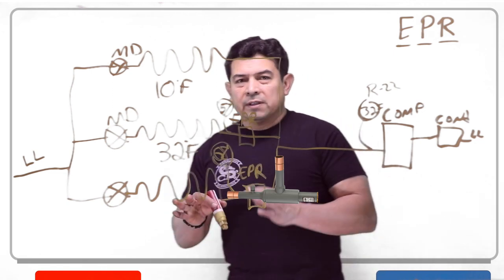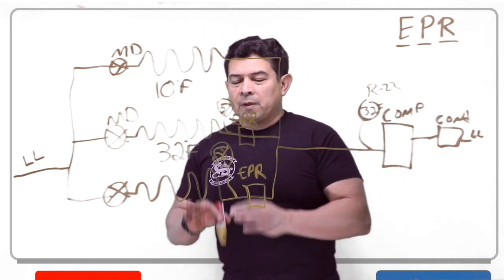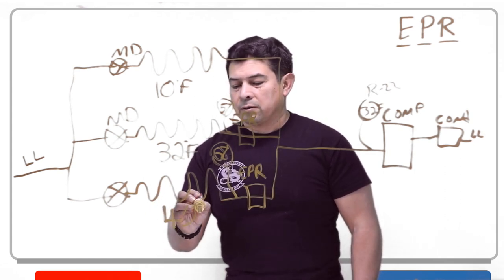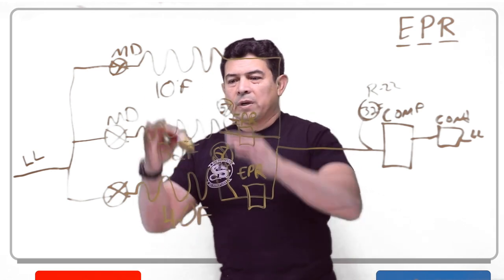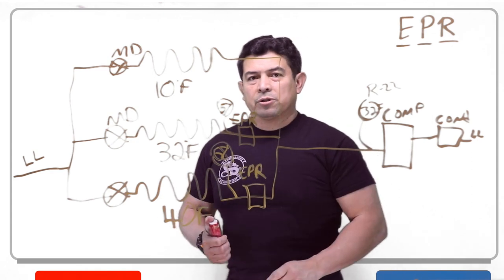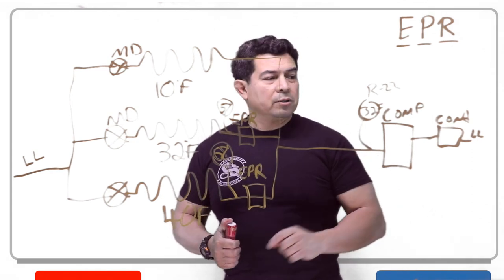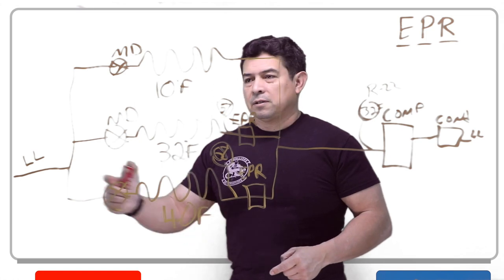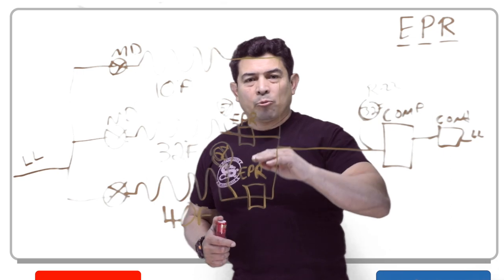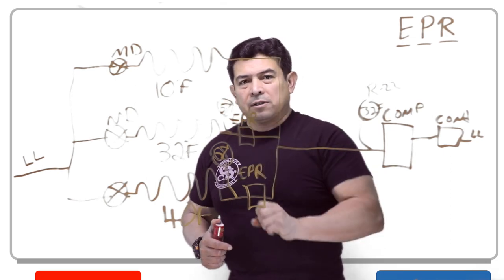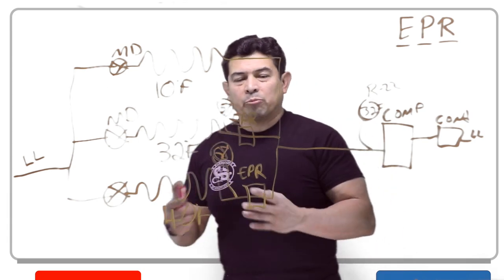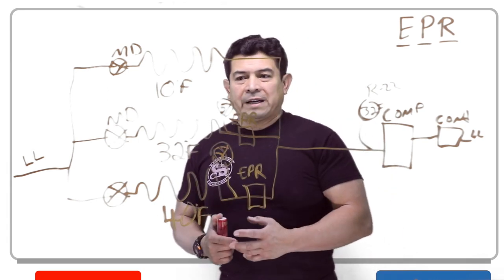Remember, we're dealing with R22 in this example. 68 PSIG cross-references to 40 degrees Fahrenheit. So now we have one, two, three boxes being maintained at different temperatures with the same compressor, the same condenser, same liquid line. We can do this by having evaporator pressure regulating valves adjusted to different pressures to give us different temperature boxes, different temperature evaporators.